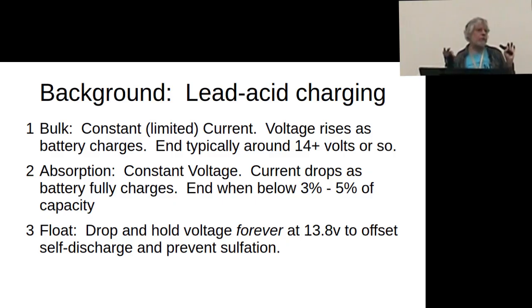The battery's charged, but now you need maintenance on it - called the float phase. Basically, you put 13.8 volts on it, the magic number. That's enough voltage to keep bad things from happening. It keeps the battery charged and prevents sulfation. It's not so high as to start decomposing water into hydrogen and oxygen, which can cause bad things. So there's a little range there, above about 13, 13.8 volts, somewhere up in there, that does that. There's also a fourth phase - equalization - but that's kind of a special case we don't need to worry about. So that's what lead acid does.